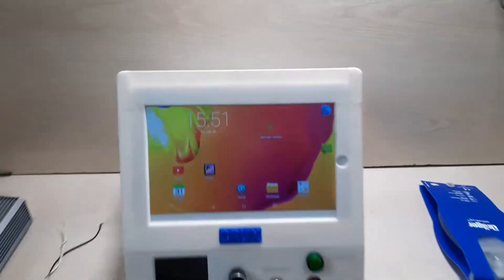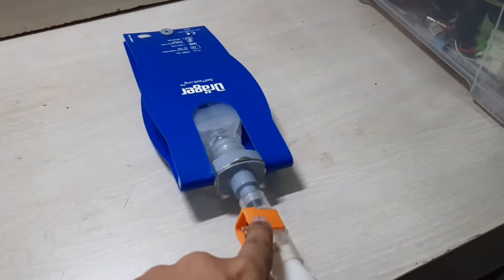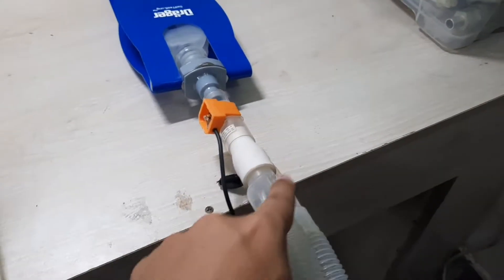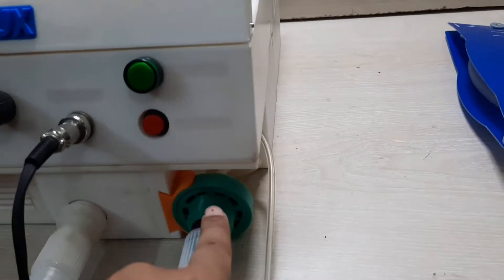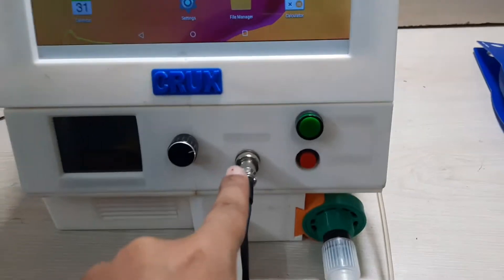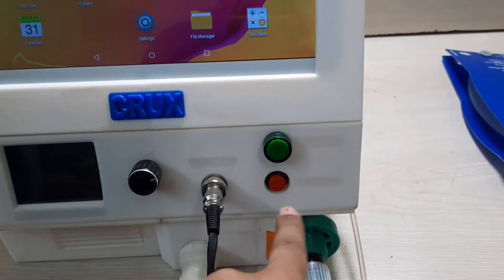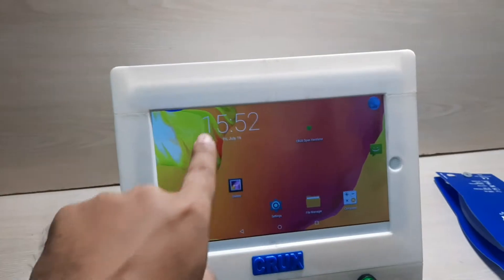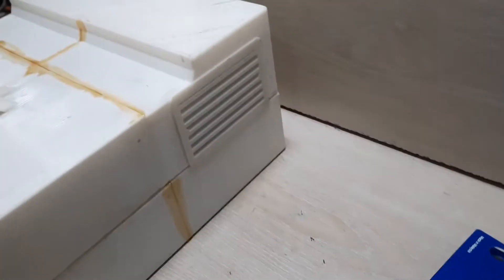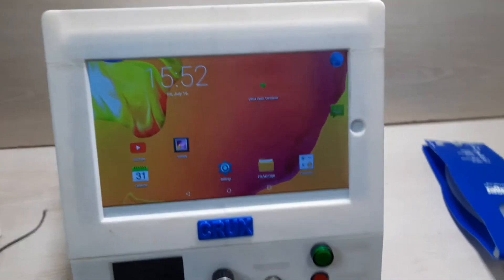So first, here you can see the test lung, the flow sensor, here is the pressure sensor probe connected here, this is the PIP valve, this is the connector port of the flow sensor, this is the reset button if needed for test purpose, and here you can see our main screen. As you can see, this ventilator is now not connected with any external power source, so it will run completely from the battery.